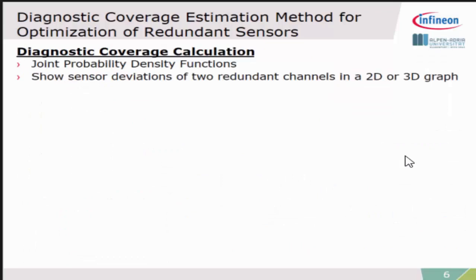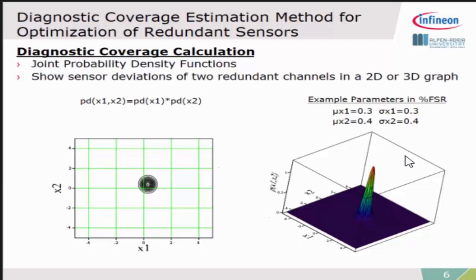Now coming to the diagnostic coverage calculations, this we did using joint probability density functions. Here is a short overview of how this looks in a 2D or 3D graph. These are the two-dimensional graphs of deviations. X1 is the deviation of channel 1, X2 the deviation of channel 2. You get then a nice joint probability density function, also superimposed with the faults, and here we can continue to calculate the probabilities.